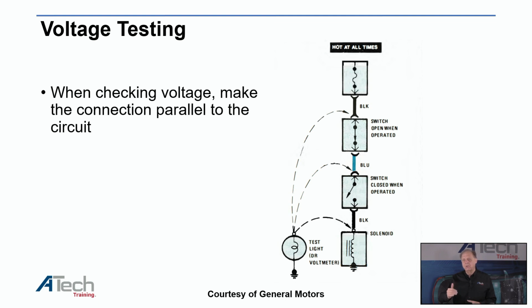So we're going to put our meter across the circuit and measure the voltage as it goes down. You can start at the bottom and go up, or start at the top and go down, depending on how you feel comfortable testing. I tend to start at the battery first to make sure it's proper, then go to my fuse or circuit breaker -- I want to make sure I have the actual voltage I need to work on the circuit.